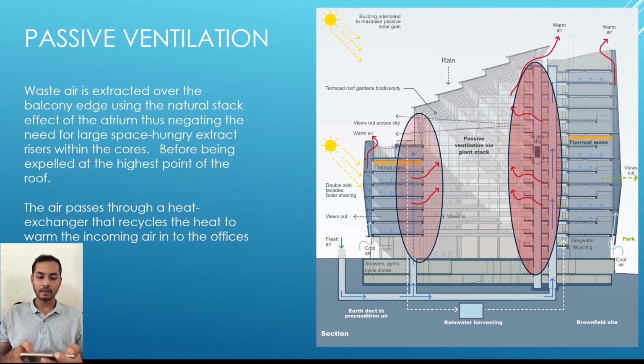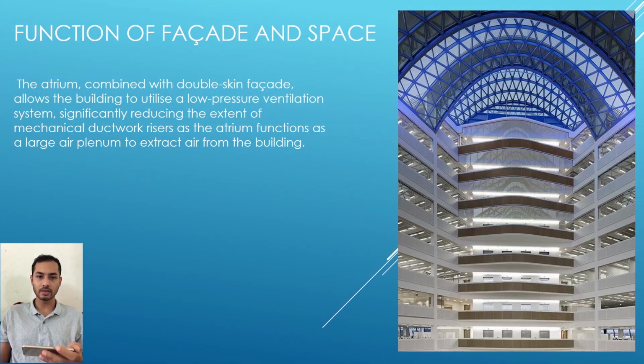For the next slide, I'll talk about the function of the facade and space. The atrium combined with the double skin facade allows the building to utilize a low pressure ventilation system, significantly reducing the extent of mechanical ductwork, with risers as the atrium functions as a large air plenum to extract air from the building. That's the function of the atrium, acting as a way to extract air from the building.